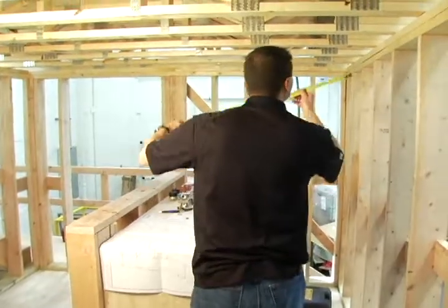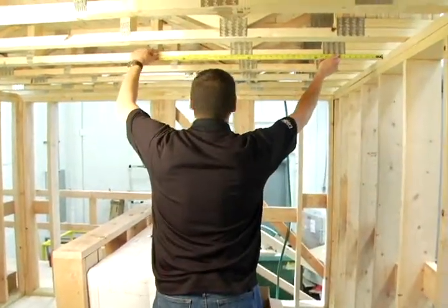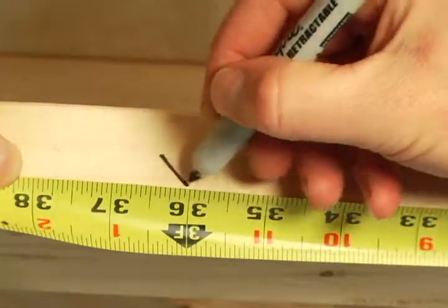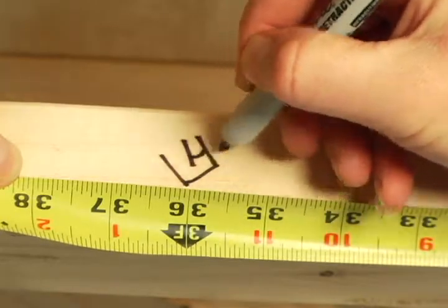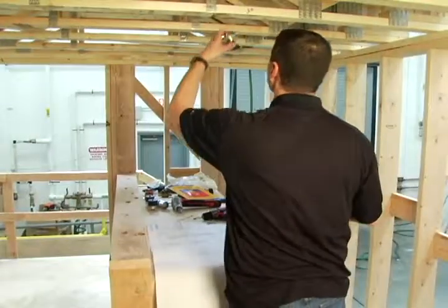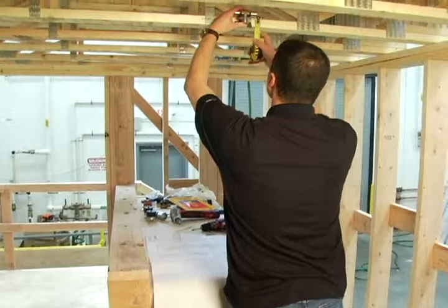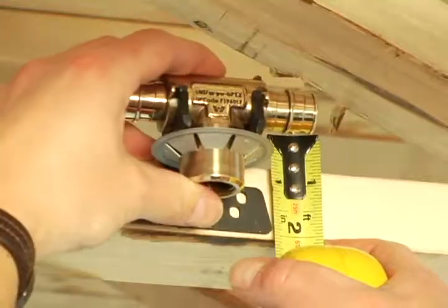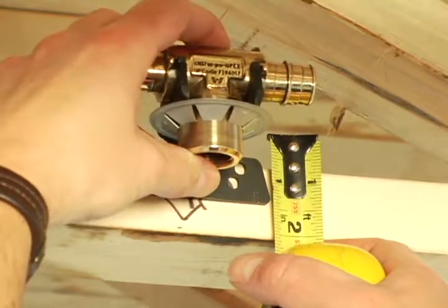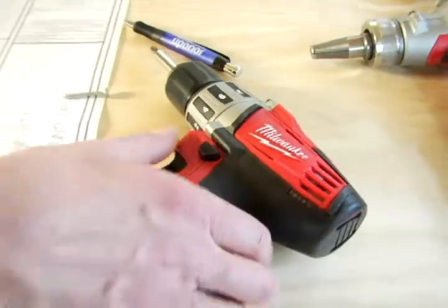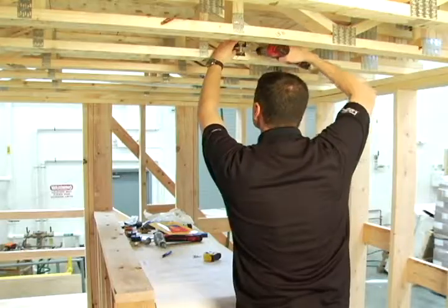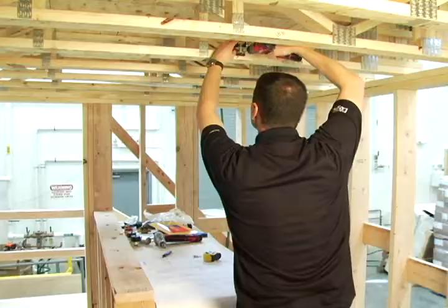Before positioning the adapter assembly, ensure that there will be no unexpected obstructions near the adapter that might interfere with the sprinkler's performance. Position the adapter, ensuring that the vertical location takes into account the thickness of the material that will be attached to the ceiling or wall. Using number 10 screws, securely mount the adapter assembly to the ceiling joist or wall stud.